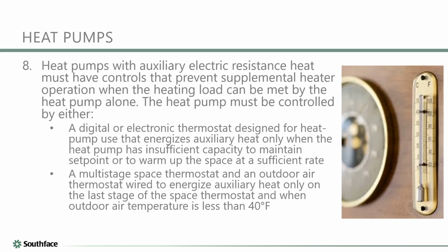Not necessarily. Because you see, what your heat pump is doing is just switching your refrigeration outside and bringing your condenser inside. Basically, that's what it's doing, right? So your condenser temperature is somewhere in the 140 degrees thereabout. As long as you can reject heat outside, the closer you get, that delta outside gets smaller and smaller when outside is cold, because you're going against, say, a 45 degrees evaporator temperature, right? So the closer you get to that number, then your capacity starts falling off.